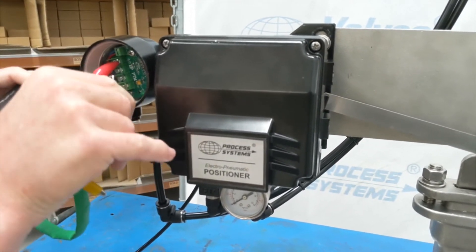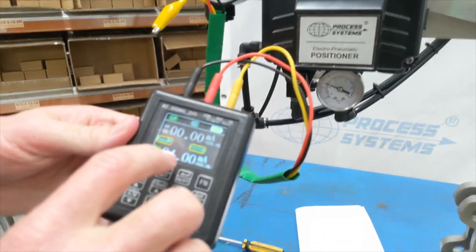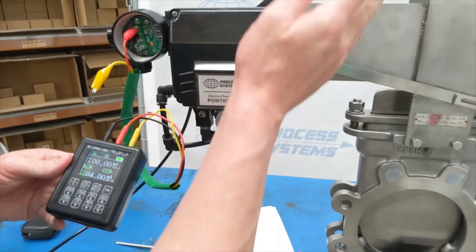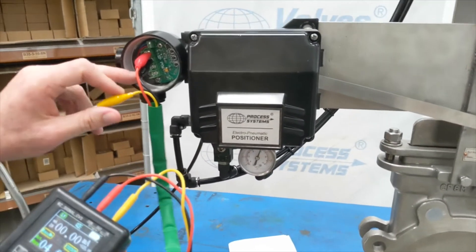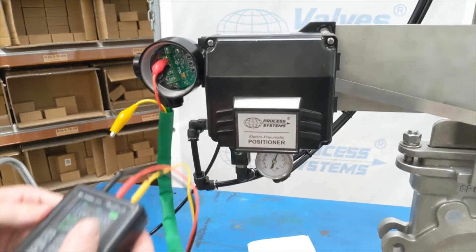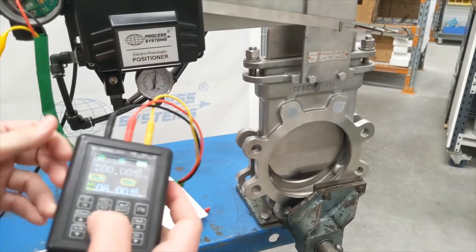We'll just put our controller on here. This unit is a 4 to 20 milliamp controller — it handles both input and output. We'll connect it to the input positive and negative. At the moment you can see it's saying 4 milliamp, so it's in the totally closed position — the zero has been set correctly. The span has already been preset, but we can double check that. The yellow clip is for the output; the negative is a common.